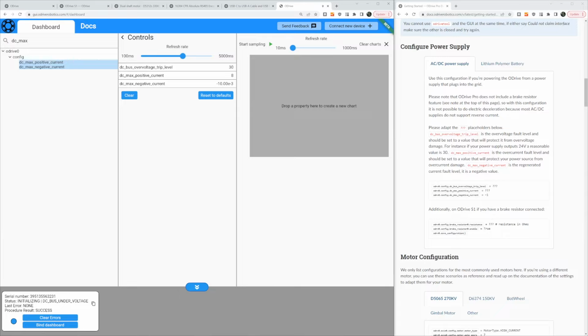And then the max negative current, that's how much current we can push back into the supply. My power supply cannot handle any current in reverse, so I'm going to leave this as the default of just 10 milliamps. This only works if you have a brake resistor, so it can dissipate the current elsewhere. If you don't have a brake resistor, you may want to set this a little bit larger, a little more negative.